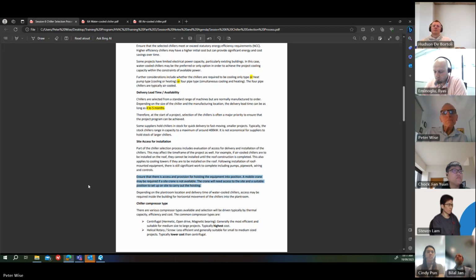And that mobile crane needs access to the site and a suitable position to set up on site to carry out the hoisting. The mobile cranes are a bit limited on how high they can lift as well. So just some other things to think about. Depending on the plant room location and delivery time of water-cooled chillers, access may be required inside the building for horizontal movement of the chillers into the plant room.